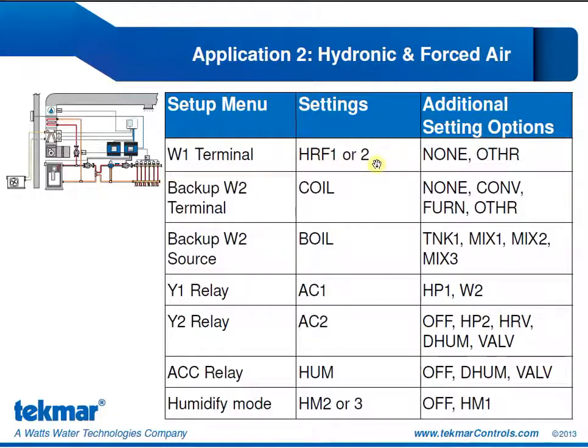Taking a look at our essential settings, this time we do have a radiant floor, so we're going to configure the W1 terminal for HRF 1 or 2, depending on whether it's a high mass or a low mass system. In this case, our backup W2 terminal is set to coil. And whenever we're setting up our backup W2 terminal to a hydronic system, we have to program what the W2 source is going to be. In this case, it's high temperature. We're setting that source to boil.